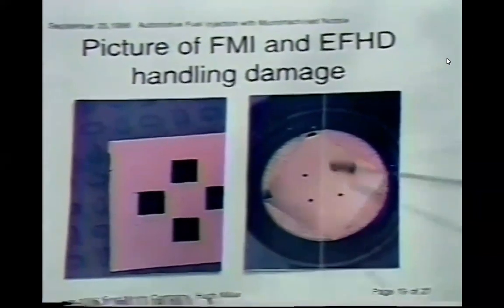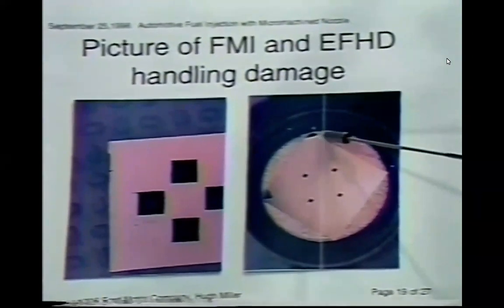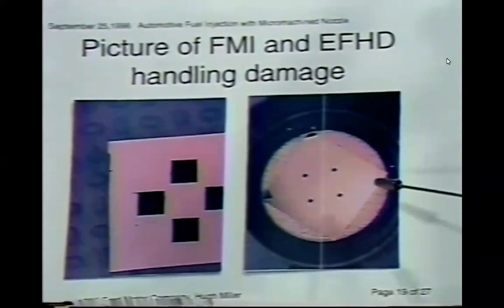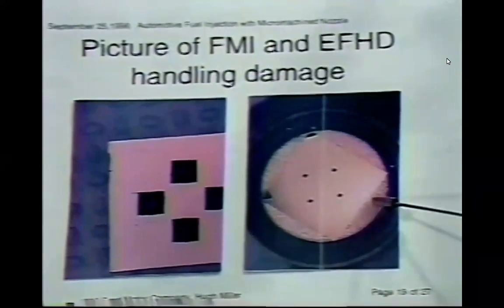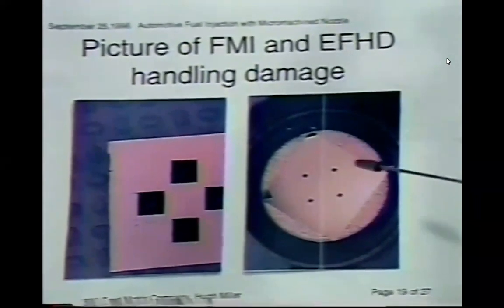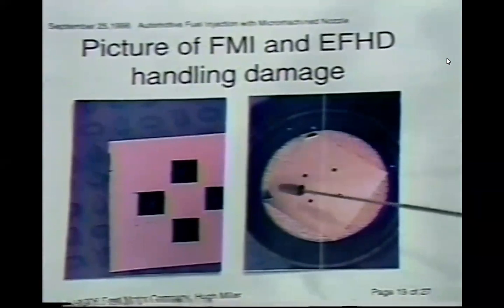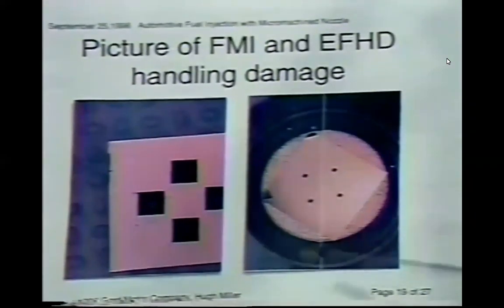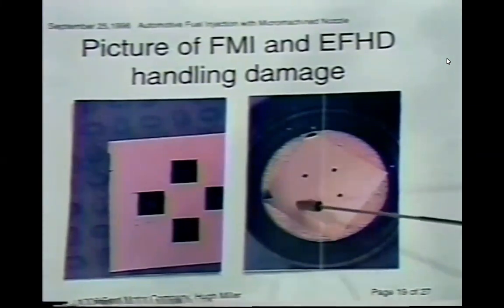In this particular case, here's a corner that's slightly knocked off in the retainer assembly, just prior to the valve body insertion. This chunk of silicon will now be placed over here, and under the pressure of the assembly and the welding operation, it could induce a moment in these particular orifices, causing a crack.